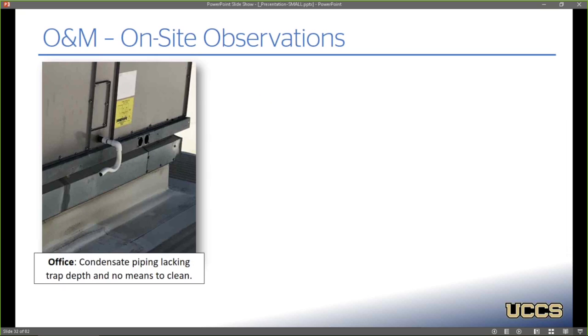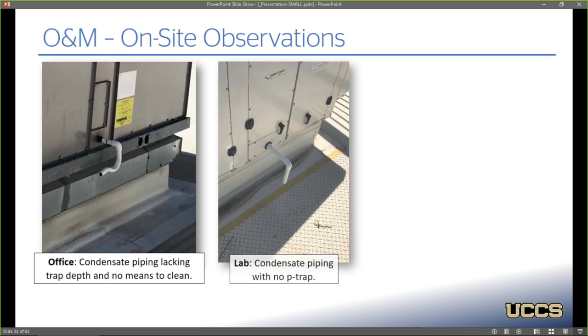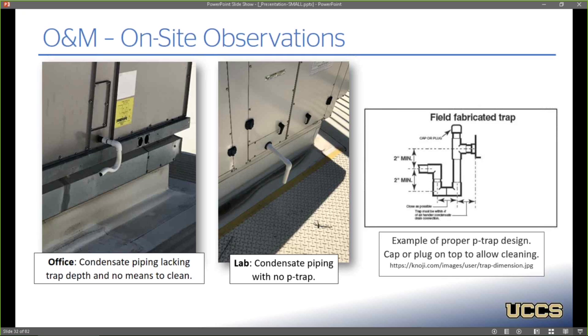Then on the office units, the condensate piping was not the best. They attempted to put a P-trap here, but it really doesn't look like it has sufficient depth to be effective. It also doesn't have a means to clean it in the event that there's a blockage. On the lab unit, they didn't even put a trap in at all, so it's just open to the exterior. And here's an example of a properly built trap that has sufficient depth for it to be effective, as well as a cap or some kind of plug on the top so you can clean it if needed. So these aren't all energy concerns, but certainly operational concerns that should be looked at.